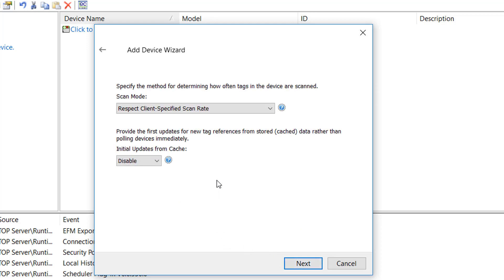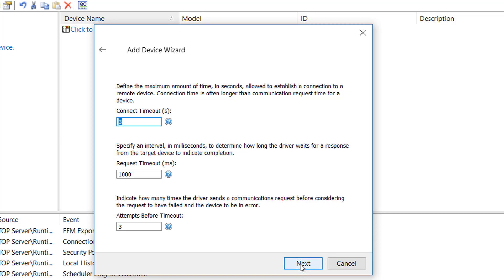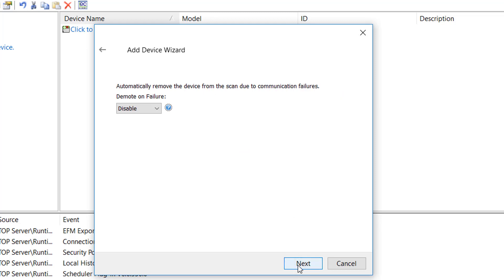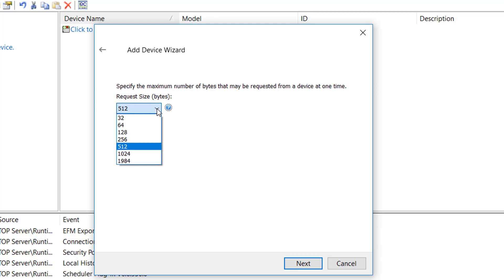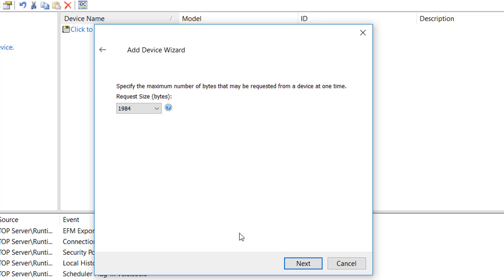Next we get to our Scan Mode settings — we're going to leave that at the default behavior of respect client-specified scan rate, which makes our poll rate be controlled by our client application. We'll keep the defaults for the timing parameters with respect to connect timeout and request timeout settings, and leave auto-demotion disabled as default. Then we get to the request size, which determines the maximum number of bytes that can be requested from the Omron controller in a single request. The default is 512, but if you're on a reliable Ethernet network you can max this out for the fastest performance. I'm going to set that to the maximum of 1984 bytes and click Next.